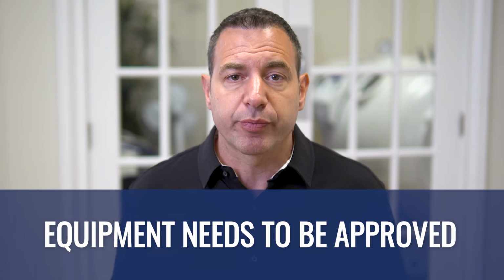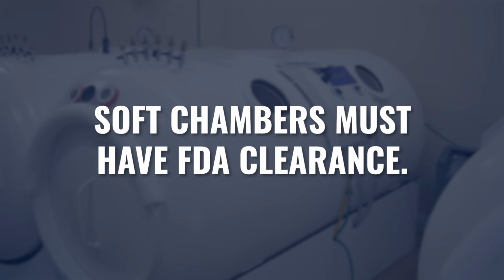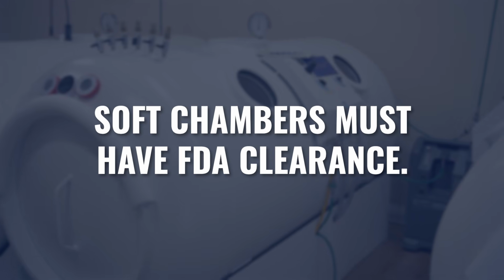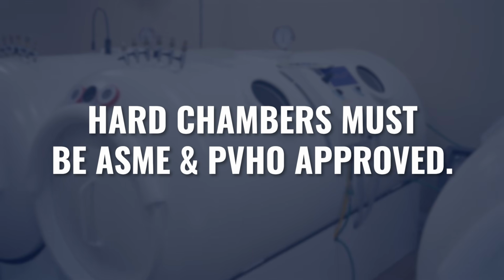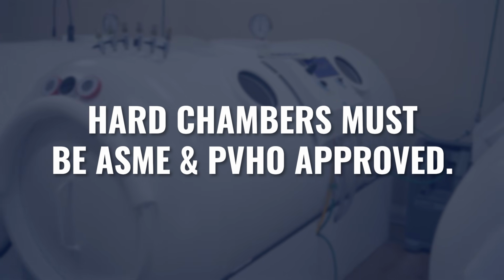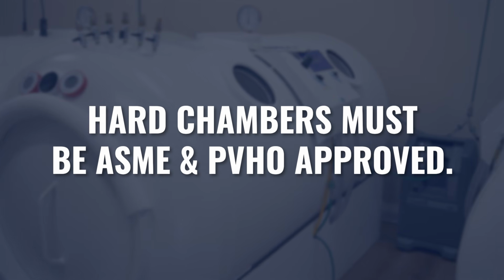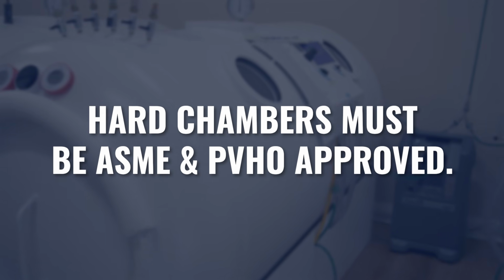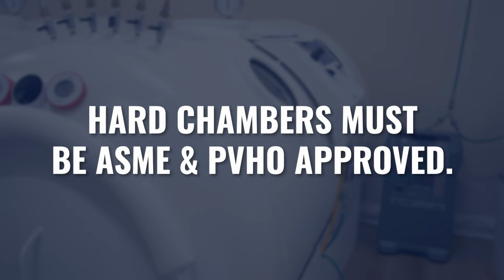But here are some of the highlights. First and foremost, your equipment needs to be approved. What does that mean? If you're using a soft chamber, that means that chamber needs to at least have an FDA clearance. If you're using a hard chamber, that means that chamber needs to be ASME, the American Society of Mechanical Engineers, and PVHO, which is a subset of ASME. PVHO is pressure vessels for human occupancy.